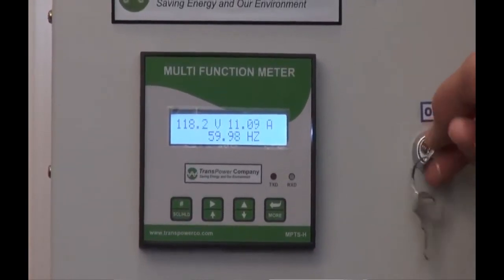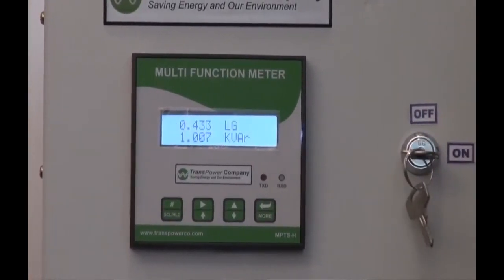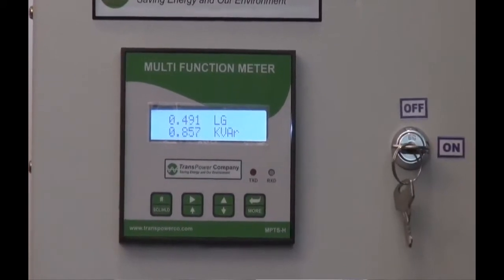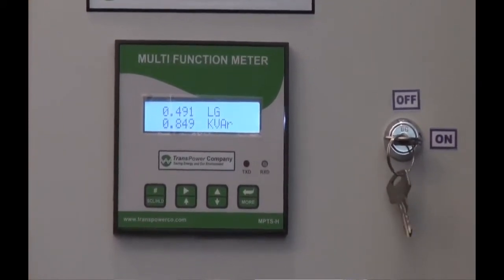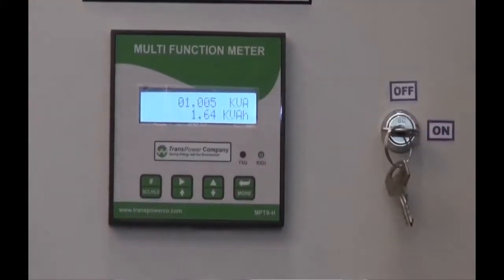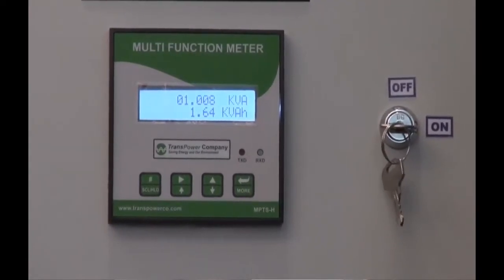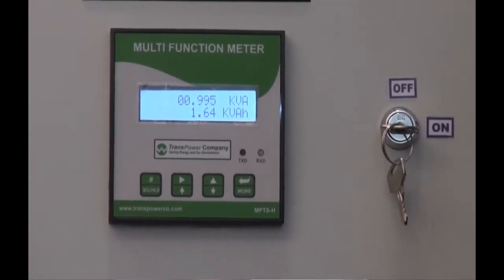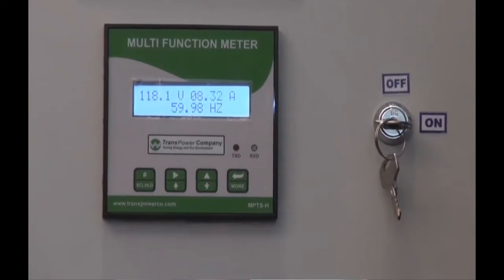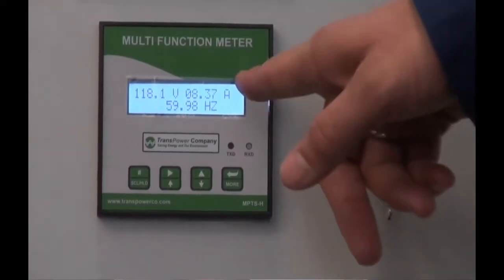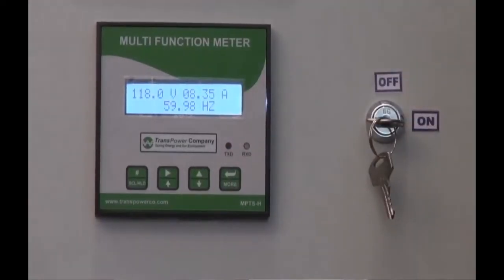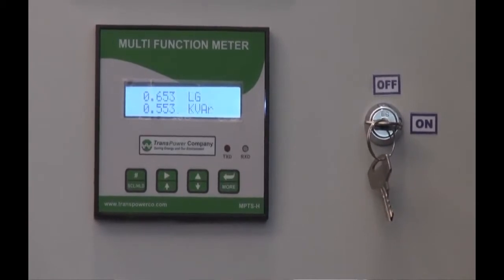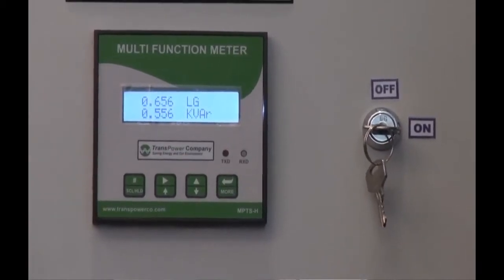Now as I turn the switch on, you're going to see the power factor immediately start to rise. It's already going to 0.5, and it'll end up at 0.98. The kVA will begin to drop to about 0.5, and the kVAR will get to about 0.2. The amps are already dropping—it's at 8 now, and it'll probably settle in at about 4 to 4.5 amps.